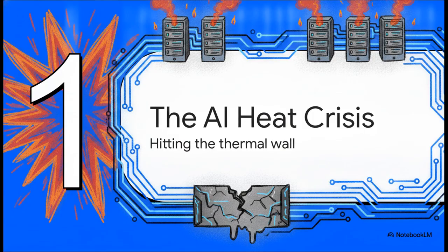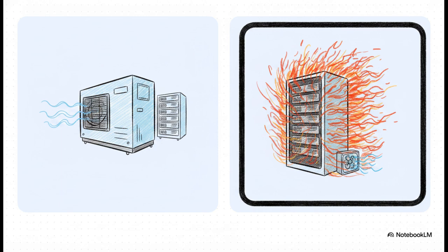All right, part 1, the AI heat crisis, hitting the thermal wall. We really need to establish exactly why the tech industry is hitting this massive thermal wall. It basically comes down to a huge mismatch. See, for decades, data centers just used CRAC units. That stands for computer room air conditioning. Essentially, they're just giant air conditioners blowing cold air down the aisles. But modern AI needs, they are completely off the charts. We're now packing multiple CPUs and GPUs into single servers, which drastically drives up the thermal design power, or TDP. Simply put, air just cannot absorb and move that much heat fast enough anymore.